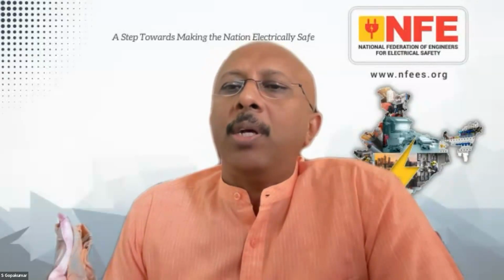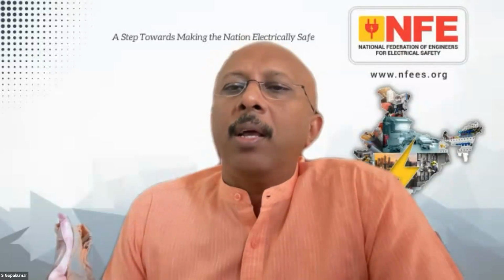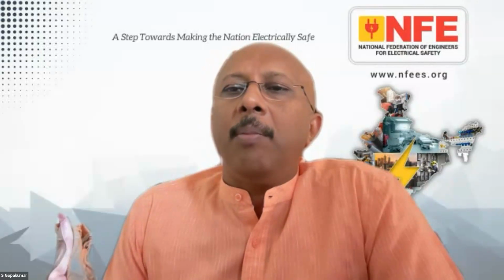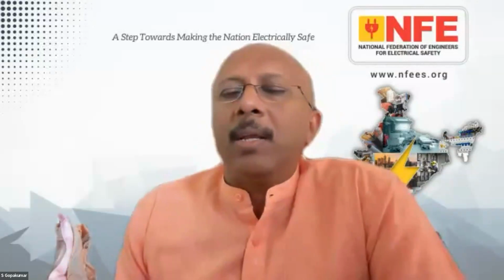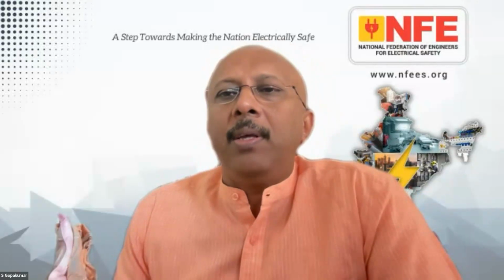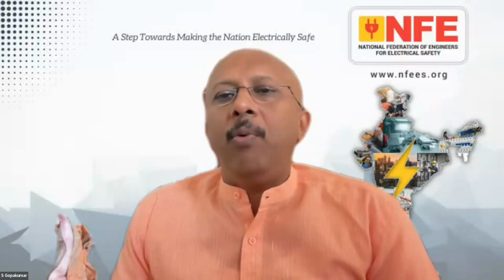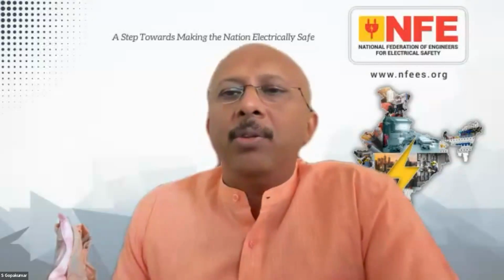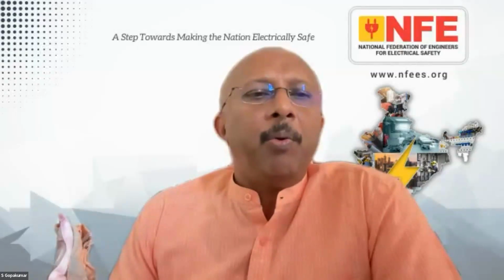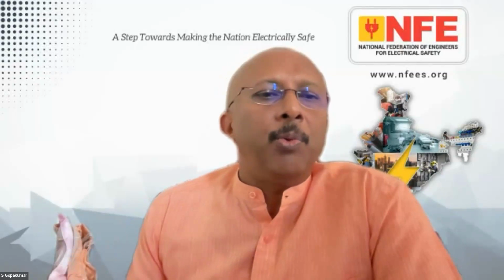We have Mr. Ullas. To avoid or eliminate shock hazard completely, why not use ELV for the elevator circuit where passengers come in direct contact with car elements? Mr. Ullas, this is also what is recommended, but equal safety is achieved or recommended in the standard. If you are using more than 50 volt, you have to use a 30 milliampere RCD. So the safety is not compromised. Now we must also realize that using less than 50 volts always is not possible, because a lot of equipment on the car top, the door drives and a lot of other equipment, use higher voltage, and even the safety circuits use higher voltage. So in high-rise buildings, using less than 50 volts is not a possibility. Okay. Because the power requirement of the car-installed equipment is much more. Yes.